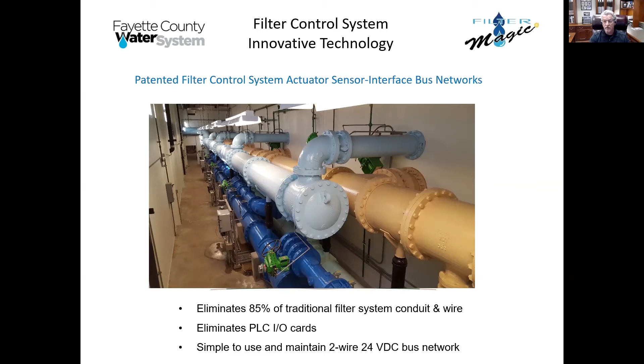So that's one way to look at it. Here's another way to look at it. You're looking at the K-torque pneumatic actuator, the effluent rate of flow that we talked about. You can see a flex conduit coming up into the bottom of it. Inside that flex conduit are the only 2 electrical terminations on that actuator, and it happens to be a 16-gauge pair of wires for the AS-i bus network.